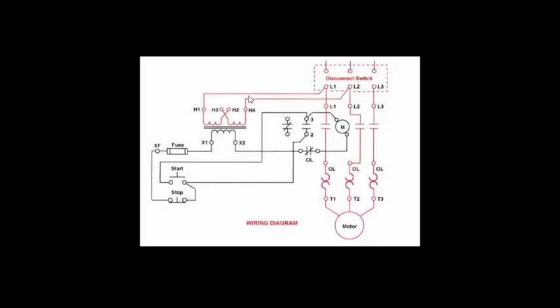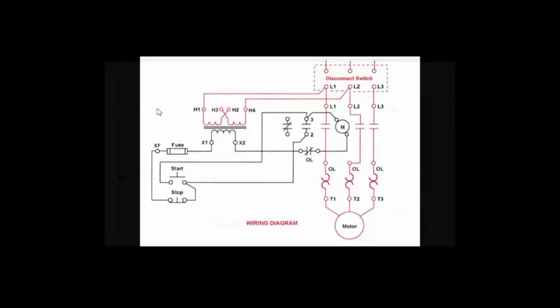And over here we have the transformer, which receives 208 volts, two phases, and steps it down to 120 volts. Then we have a fuse, a normally closed stop push button, and a normally open start push button. And this is the wiring diagram, and this is a good physical representation of what would be in the field. This is very helpful for wiring up the circuit. To make it easier to understand the circuit, and for the purpose of troubleshooting, we'll look at the schematic next.